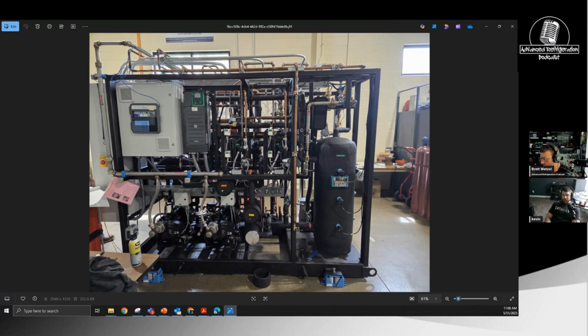Medium temp compressor on the drive, super standard setup. The only thing that was a pain on this was that emergency switch on the side of the panel. I had to set it up so it kills the boilers and at the same time shuts the rack down, but in a safe manner. I had to kill the evaporators and put a 3 minute time delay on the pro kill so it would pump down and shut off, then I killed the compressors, because if I just killed it, it would just start popping reliefs.